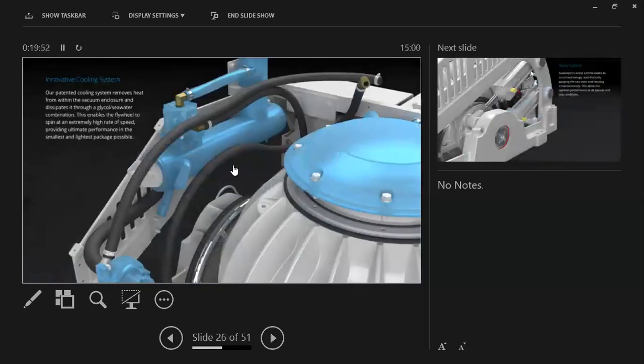We do have a liquid cooling system. We bring raw water into a heat exchanger, just in and out, with a closed glycol water loop. A small glycol pump circulates a glycol water mix through the cooling caps, cooling the bearings, the electronics, the entire system. This lets you tuck them into tight spaces without worrying about a lot of ventilation. They run very cool, surprisingly, considering how fast it's spinning. It could run all day on a hot day and you can put your hand on it, and it's just warm. They don't get very hot at all.